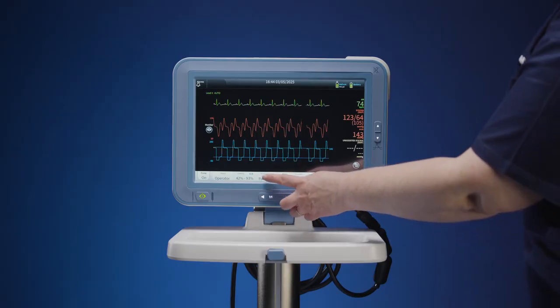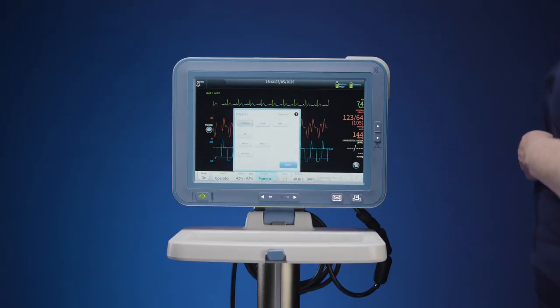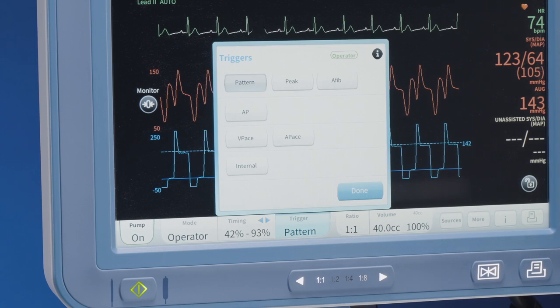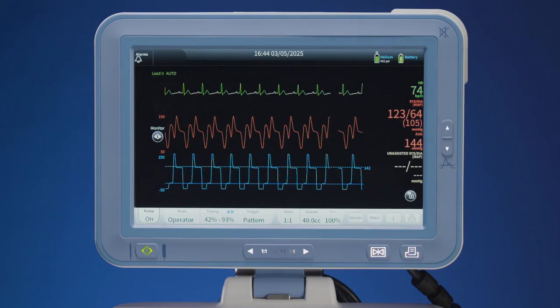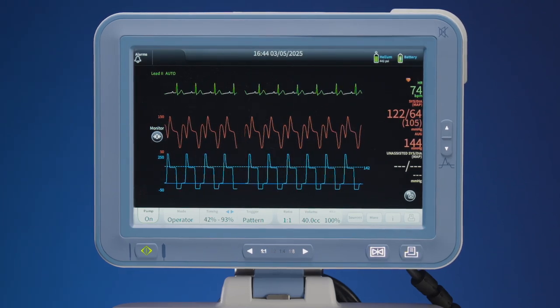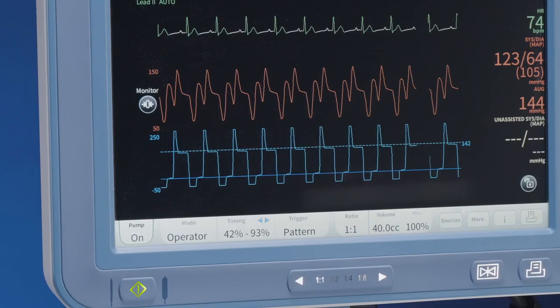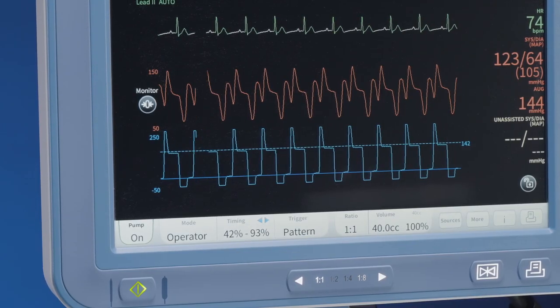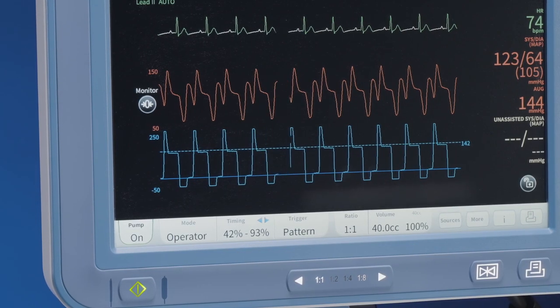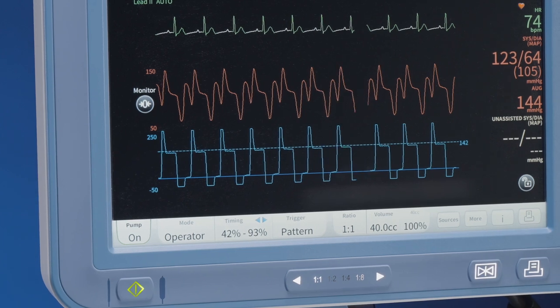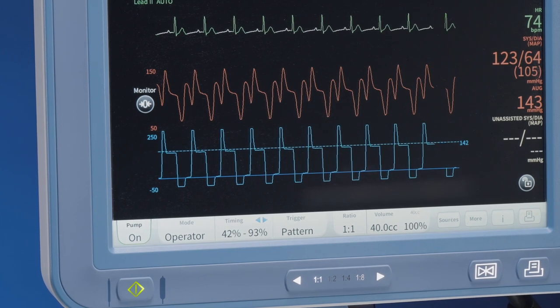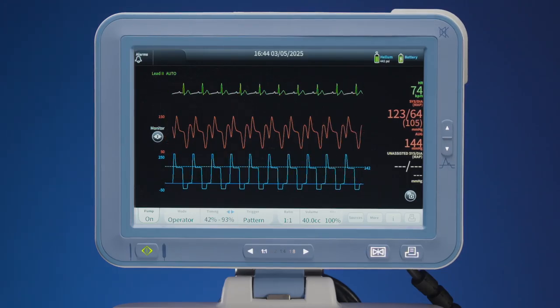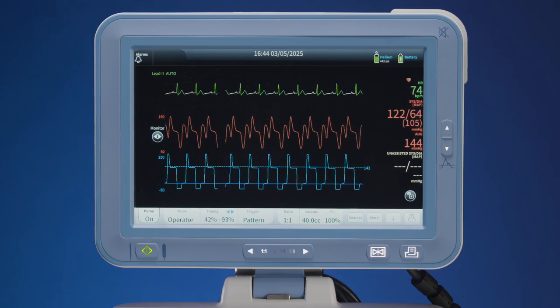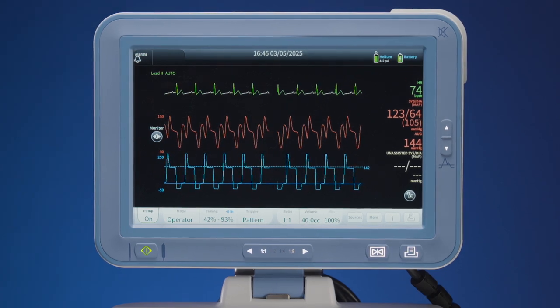The user can also select and change trigger modes, and these can be changed whilst pumping. In most cases, more than one trigger mode will work with a cardiac rhythm. The user should assess both the trigger reliability and timing accuracy to determine which is the best trigger to use. Note, the internal trigger mode should only be used if the patient has no myocardial activity and/or ventricular ejection. The user must be in operator mode to select the internal trigger and then confirm to select this trigger mode.